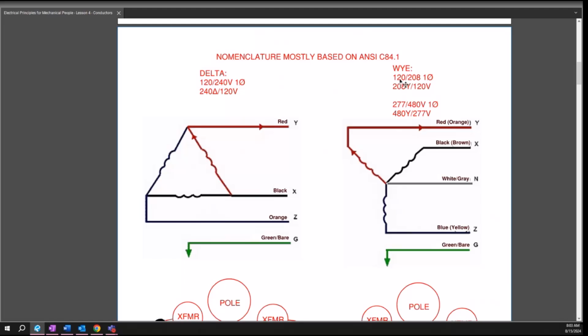120/208 single phase is pretty rare, I've seen it a couple times. It's normally a single transformer, sometimes two depending on how much they need. Same with 277/480 single phase, usually a single transformer, sometimes two. I wouldn't rely solely on one or two transformers up on the pole, because there are a lot of other configurations out there that I'm not touching on here, I'm just covering the most common things. So if you look up at the pole and see two transformers, there may be something else going on, just do your homework or call me or somebody else.